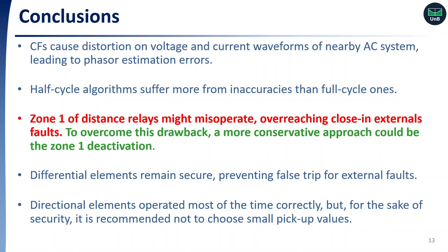As conclusions, we can point out that commutation failures cause distortion on voltage and current waveforms of nearby AC systems, leading to phasor estimation errors. These errors are even more aggravated for half-cycle algorithms, revealing that the use of short data windows may be an issue for protection schemes in these scenarios. These errors may lead Zone 1 of distance relays to misoperate, overreaching close-in external faults. In order to overcome this drawback, the Zone 1 reach can be reduced, or, as a more conservative approach, Zone 1 can be deactivated.